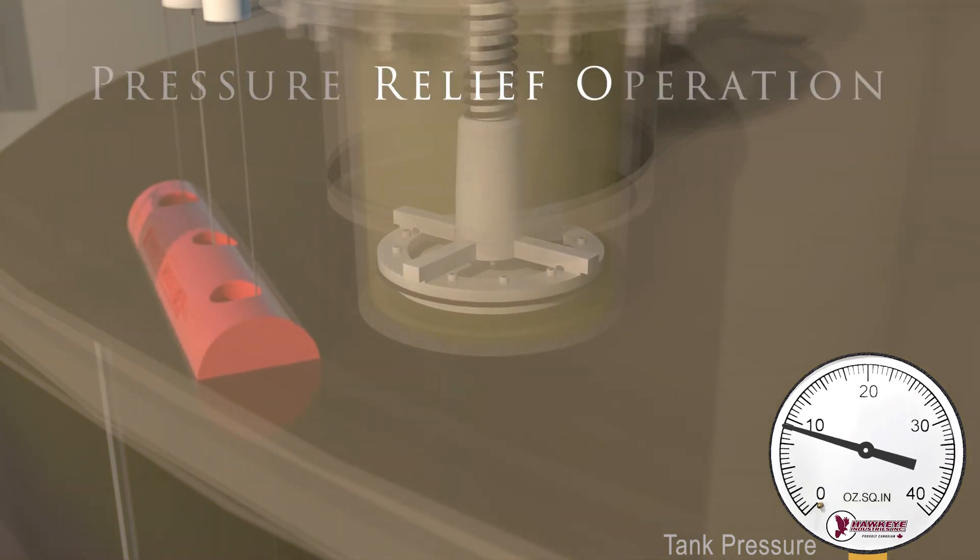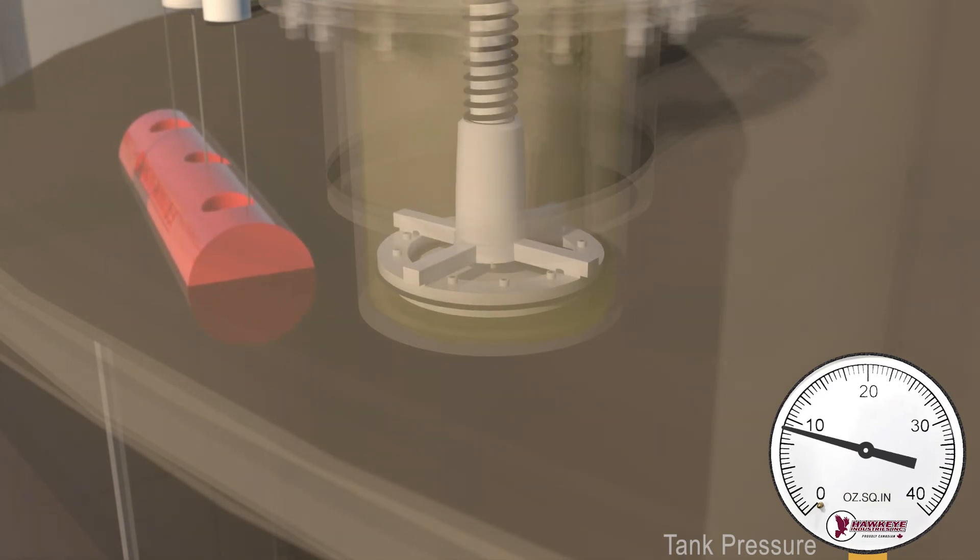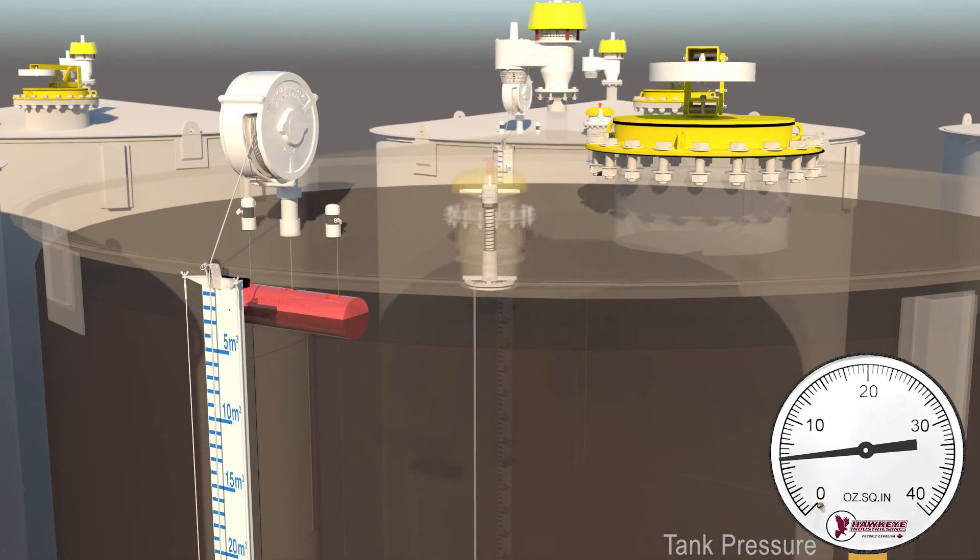As pressure increases, the spider cage continues to lift until it's able to control the flow of gas. As fluid flow stops and venting reduces pressure in the tank, the spider cage reseats as tank pressure drops below the 6 ounces per square inch relief setting.